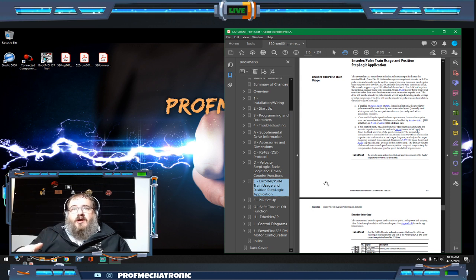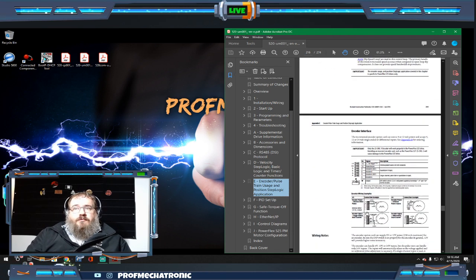We can also incorporate an encoder, taking the encoder pulse train and putting that right into the VFD. So the VFD can take care of all that encoder information and feedback, turning this VFD into a little bit more of a servo-driven system. Where it is now more closed loop, instead of just open loop where we send it to the drive, let the drive run, let the motor turn, and assume it's doing what we ask it to do. There's no real feedback. But taking this encoder pulse train for step logic, we can bring that right back to the VFD and close that loop off.